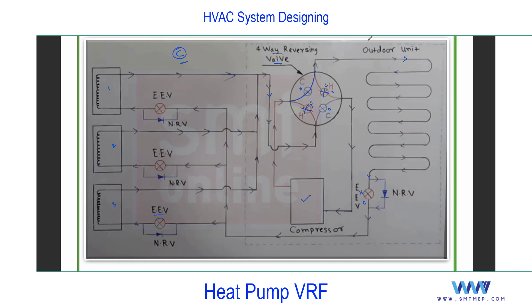Now for heating mode - I'm using red color to show this. In heating mode, two valves are in closed position and the other two are open - the opposite of cooling mode. The cycle still starts from the compressor. The compressed refrigerant at high temperature and pressure travels along the line, but now the valve that led to the condenser is closed, so it is redirected through the reversed path directly to the indoor units.